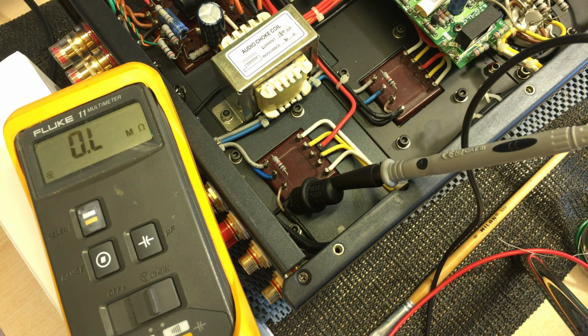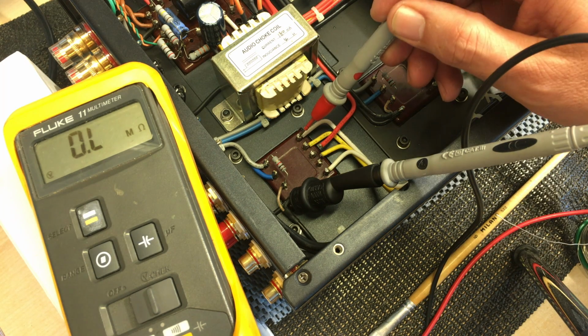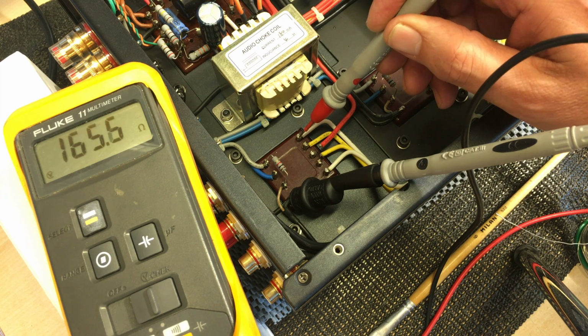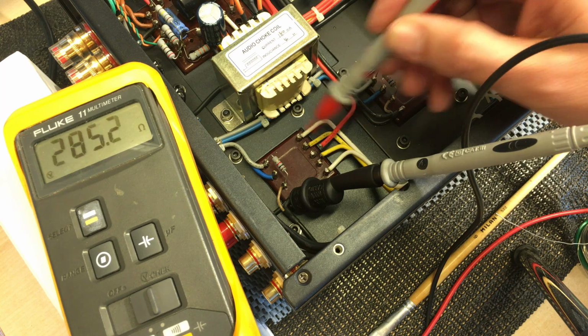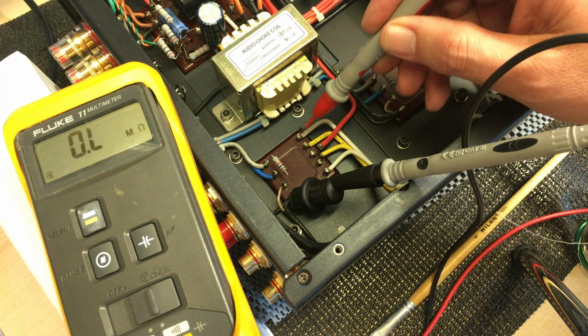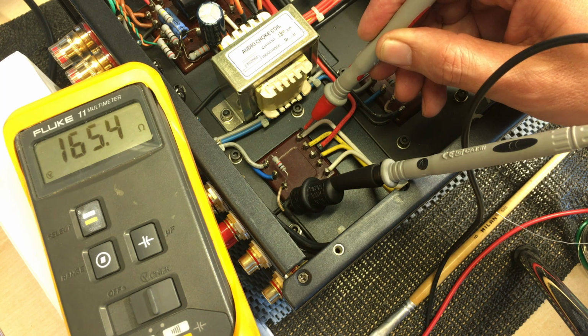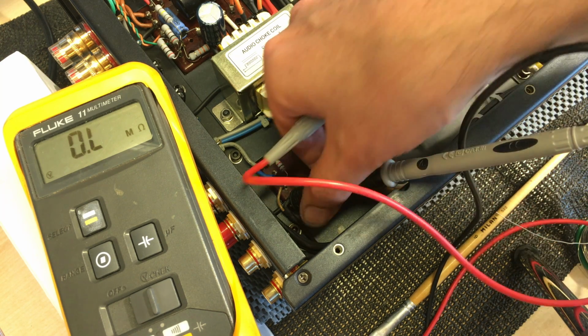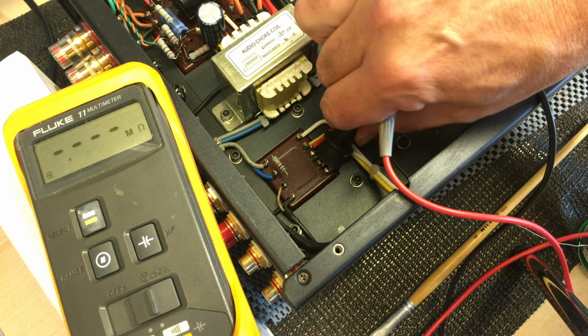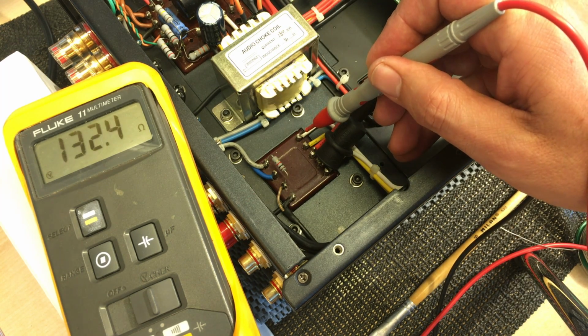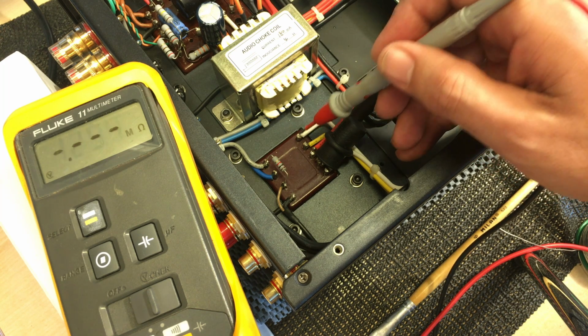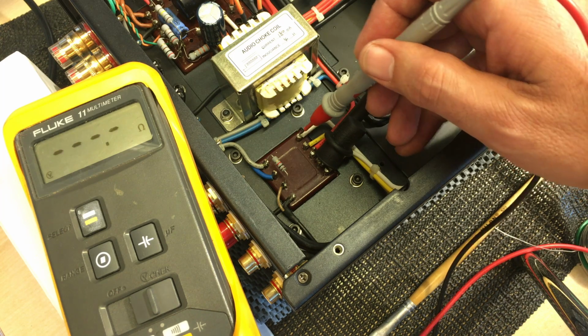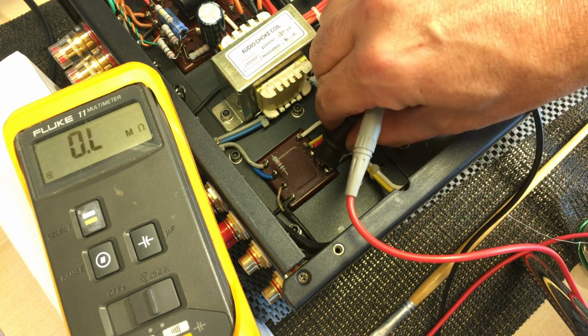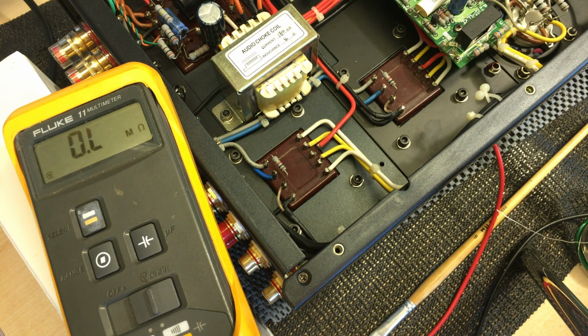Because it's not 0 ohms - if you look at all the others, they're not shorted to ground at all, they're just at the normal winding resistance between that point and this one. That one is 36 ohms, that there is 166, call it 130 ohms difference. If I connect this point to there, I get my 130 ohms. So these others are at the normal winding resistance to that point inside the transformer. I think we've found the source of the problem, and it's just a matter of taking the transformer out to see if we can find anything.